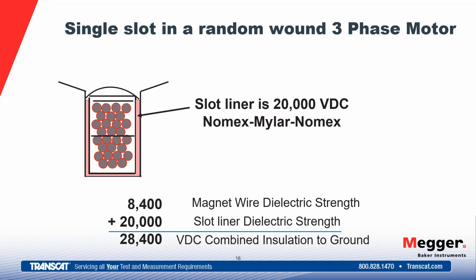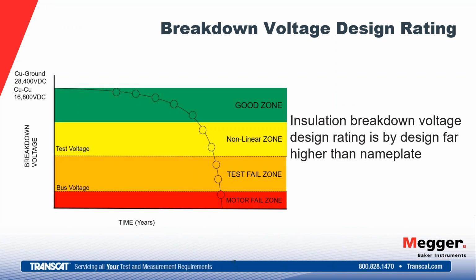So for a 460 volt motor, NEMA would tell us that the magnet wire's dielectric strength, so the insulation around the wire, is going to be at 8400 volts DC. The Nomex itself, and this particular Nomex being used here, is at 20,000 volts DC. We combine those two, the 8400 from the magnet wire insulation and the 20,000 from the ground wall insulation, and we have a combined strength of 28,400 volts DC to ground. So that's where that motor starts in its life. It was designed to start there. So we have a breakdown voltage well above our bus voltage at this point in time.